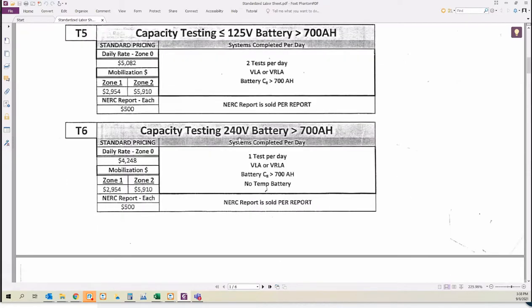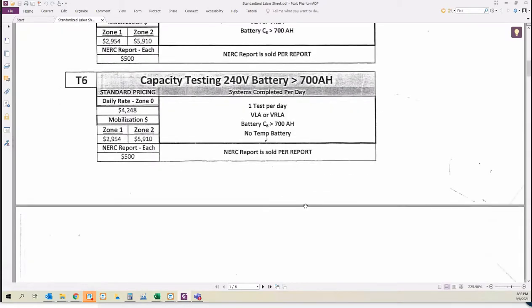A 240 volt or higher system, they can do 1 test per day, but that's without including the temp battery, because putting in a temp battery would force them, via OSHA standards, to go to a second day. So if they do require a temp battery on a string this large, we're probably going to have to quote a second day. Even if you can't stop a cap test, they're going to push them so far into the day that we'll have to charge for it. It'll basically be pulling a double.